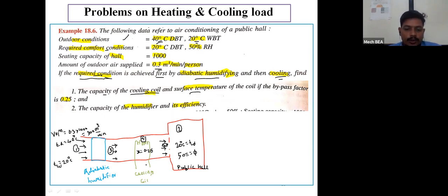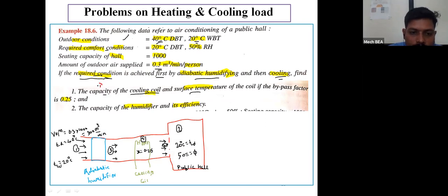So what do I have to find out here? First of all, I have to find out the capacity of the cooling coil. Second, I have to find out the surface temperature of the cooling coil, and for that purpose they have mentioned the bypass factor as 0.25. Then the third thing I have to find out is the capacity of the humidifier. And the fourth thing I have to find out is the efficiency of the humidifier.